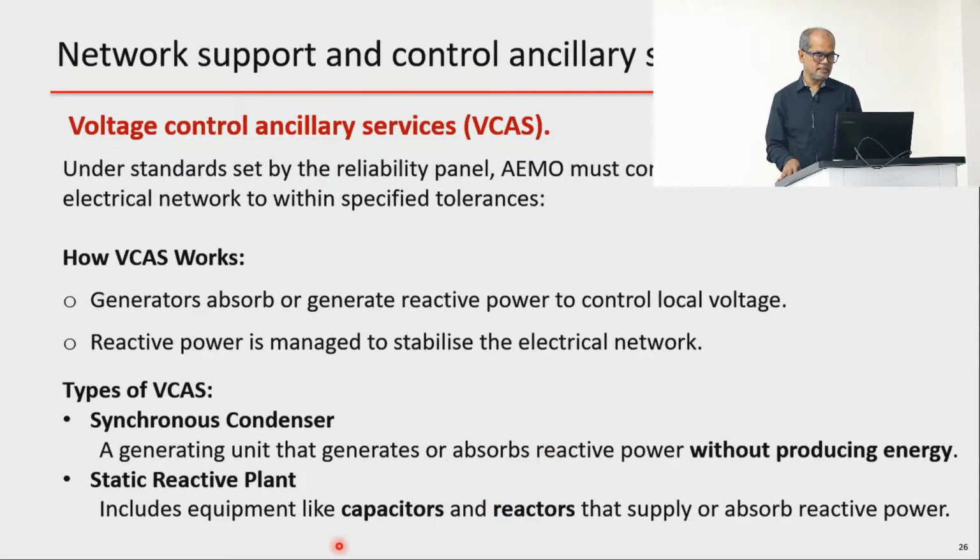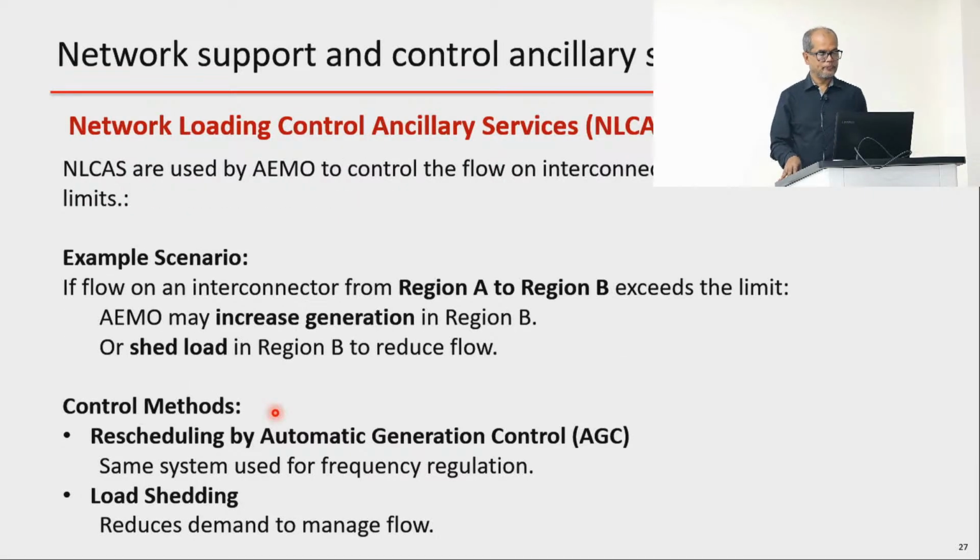But in many networks you also find synchronous condensers. And people are thinking, even in Australia, and might be other countries also, that when normal generators retire from the system, because we are phasing out coal and other things, why not use that normal synchronous generator as a synchronous condenser?